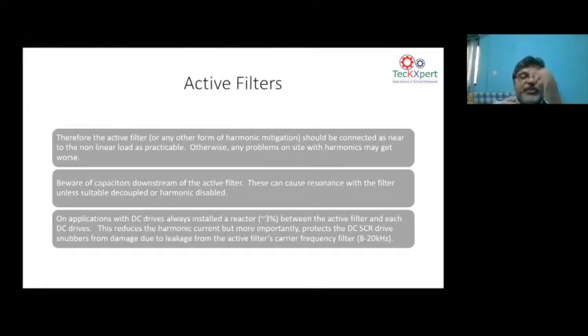Therefore an active harmonic filter should be connected as near as possible, because again, where to install an active harmonic filter is important. It's always good to put an active harmonic filter near the source of the problem. If you have a lot of VFDs downstream in the network, it is better you put an active harmonic filter near those VFDs rather than at the main LV panel. When you put it at the main LV panel, number one, it increases the size of the filter, because you need to take care of a lot of other factors. And number two, as I said before, it's a low source impedance, so a lot of harmonic currents will start flowing. In the process, downstream of your main LV panel, your harmonic distortion will still remain high, even though the harmonic distortion is low at the main LV panel. So it is better to put an active harmonic filter near the source of the problem.